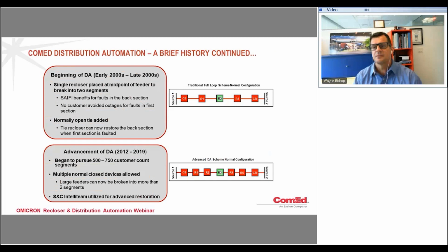Let me talk a little bit about our 12 kV DA program. So beginning of the early 2000s, we started to install reclosers at midpoints of feeders to break them into 2 segments, which definitely helped the SAIFI benefits for faults in the back section. However, there were no customer-avoided outages for faults in the first section, and the whole feeder would trip. Then we started to install the normally open tie, which can now restore the back section when the first section had faulted.